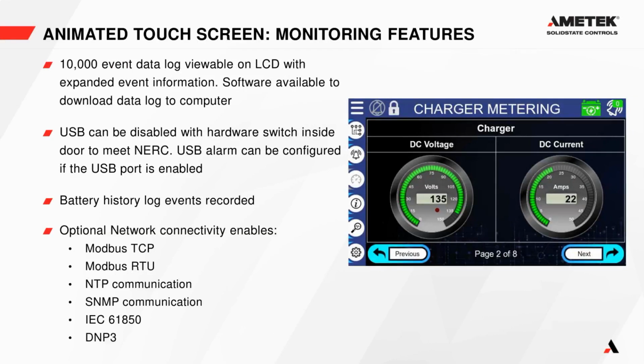We also have some monitoring features on this new charger. We have a 10,000 event data log on the LCD, with expanded event information. So you can click on a data log event and see what the system voltages, currents, temperatures, and everything were at the time that the event occurred. You can also use our SCI Link software to download this data log to a computer. Or if you have the Ethernet communication option, you can download it from a website by going to the IP address of the system and downloading it there.